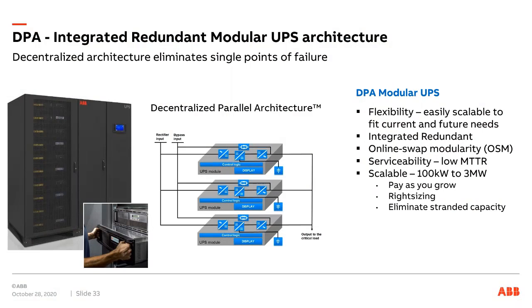So, summing up on the modular, and that is the ABB Modular UPS, it is based on the generation 2 modular design. As I mentioned, the engineers at ABB who developed this, and that may sound wrong, didn't invent anything new. This had already been done once before with monolithic UPSs, or paralleling, going from a centralized system with a system control cabinet to a decentralized one where we could parallel single UPSs. That's the same thing. ABB took that step with the modular.